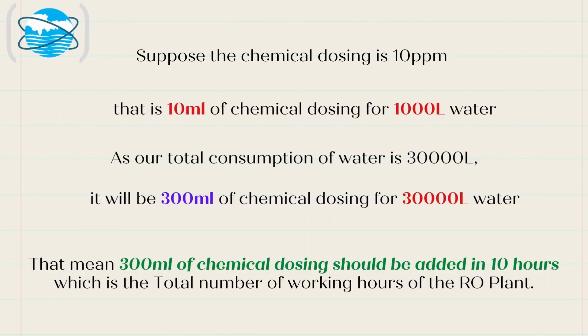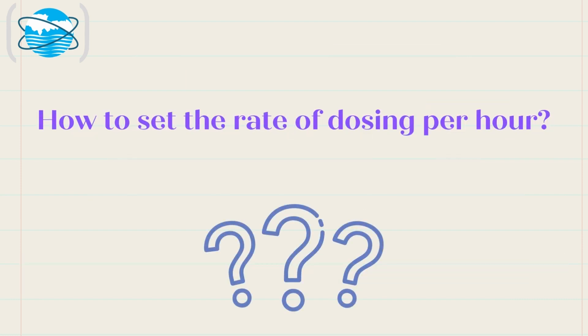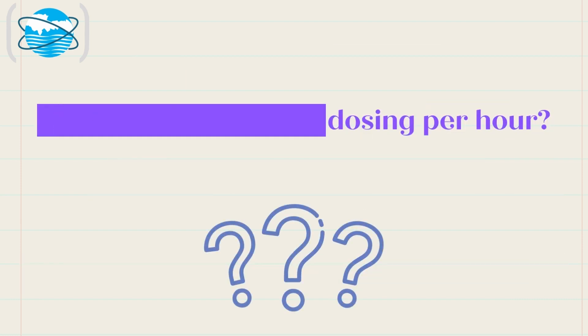Suppose the chemical dosing is 10 ppm, that is 10 milliliters of chemical dosing for 1,000 liters water. As our total consumption of water is 30,000 liters, it will be 300 milliliters of chemical dosing for 30,000 liters water. That means 300 milliliters of chemical dosing should be added in 10 hours, which is the total number of working hours of the RO plant.